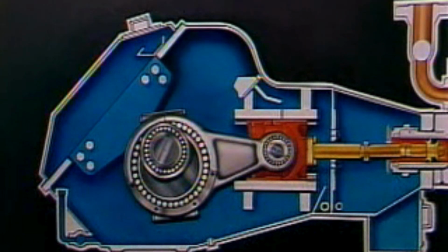The pump needs to be stopped for 5 minutes before you check the oil level. While you're waiting, drain the mud trap. The mud trap collects foreign material, water or mud, for example, which might condense inside the pump or leak through damaged rod wipers. If this trap isn't drained daily, these contaminants can build up and flow over the trap into the crankcase, where they'll cause serious damage to the gears and bearings. It's a lot easier to open a drain cock now than it'll be to replace the parts of your power end later. As soon as oil alone is draining from the trap, you can close it back up.